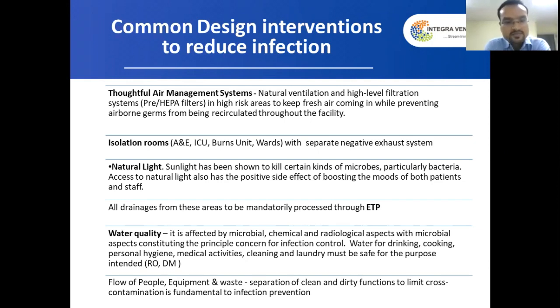If we take the example of water, there can be a lot of waterborne disease, and water requirement is very high, almost 500 to 600 liters per bed per day. The water requirement is of different categories: we need general filtered water for general areas, but in critical areas we need RO water and demineralized water, such as in the sterilization department for sterilizing instruments. For dialysis, we need RO water.